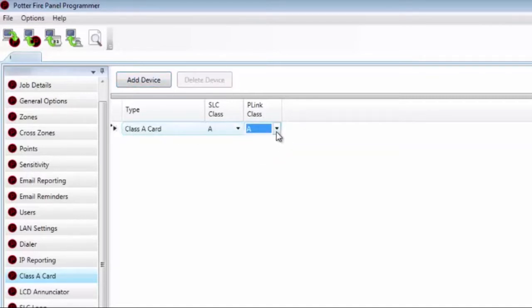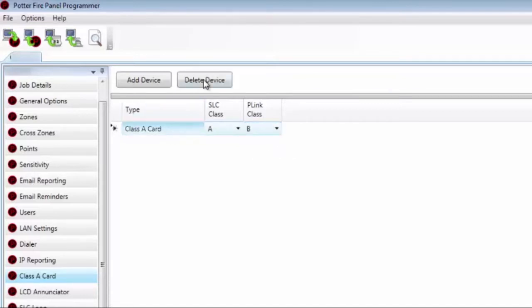If you just want your SLC to be Class A, the P-Link can still be Class B. The notification appliance circuits are not shown here — those circuits need to be wired either Class A or Class B, and each can be wired individually. For example, on the IPA-4000, NAC-1B can be Class A and NAC-2B Class B. It is simply how it is wired. To delete the device, click on it and select Delete Device.